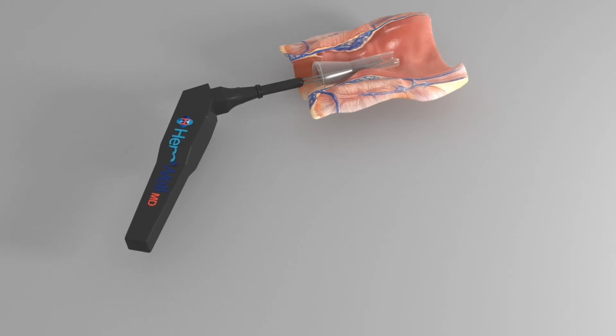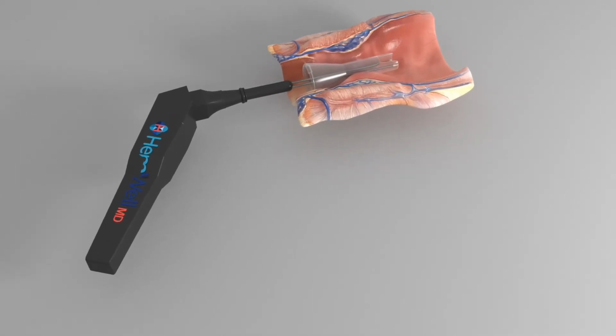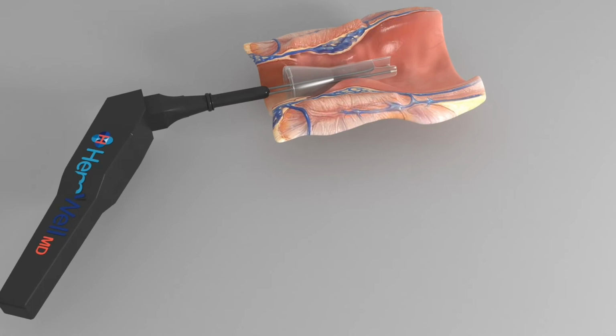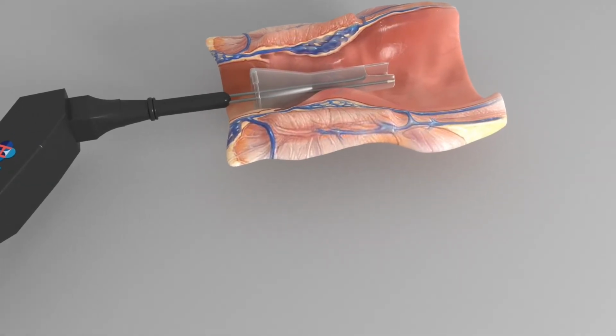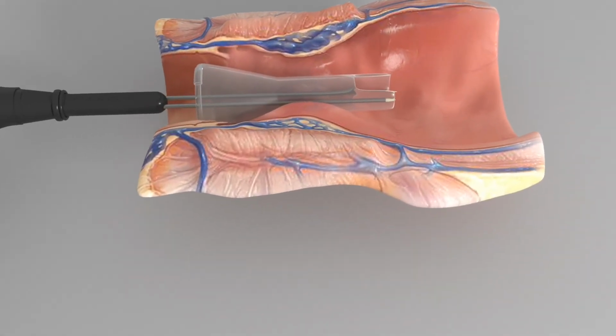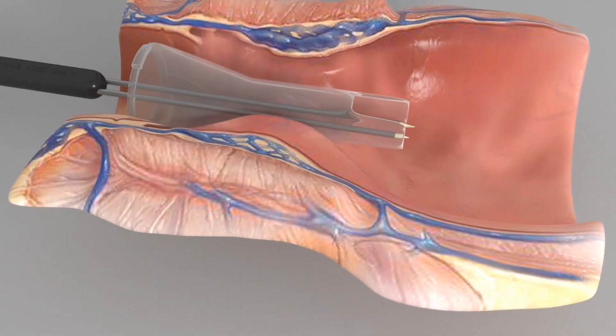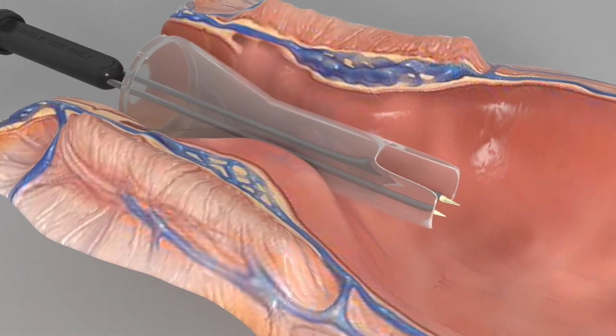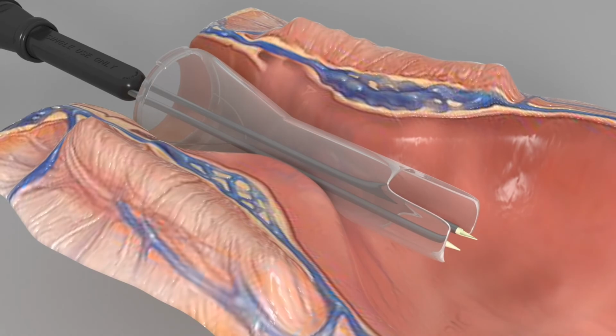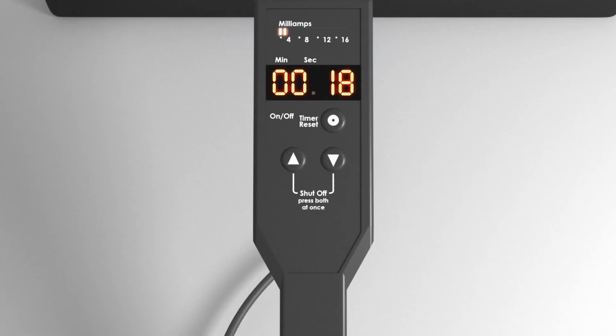Insert the probe through the anoscope and rest the probe as high on the proximal end of the hemorrhoid as possible and above the dentate line. Note, the probe should not penetrate the skin. Constantly ask the patient for feedback to assess their comfort level. Slowly increase amperage while monitoring patient's comfort level. Note, time interval is based on the grade of the hemorrhoid and the amount of amperage delivered. Refer to operations manual.